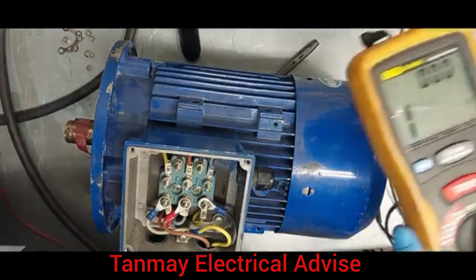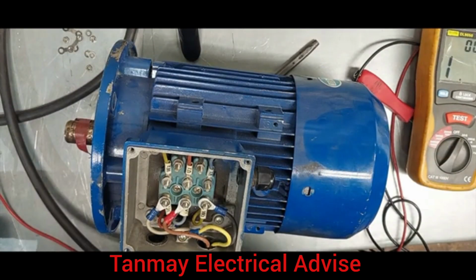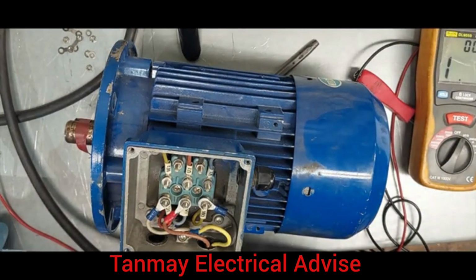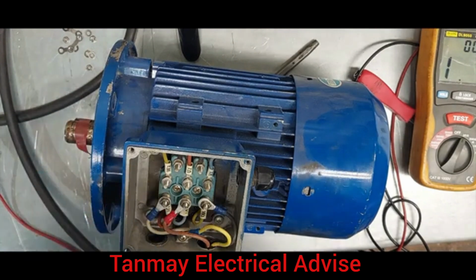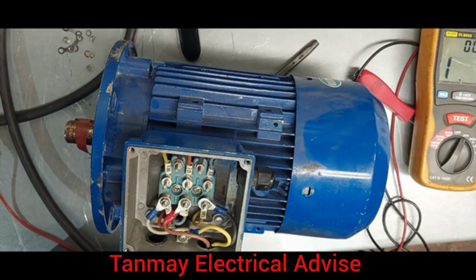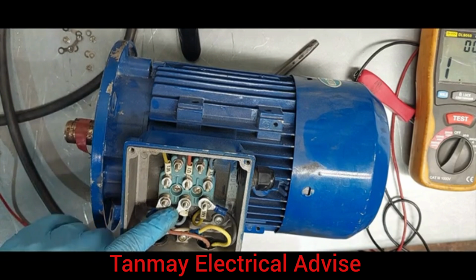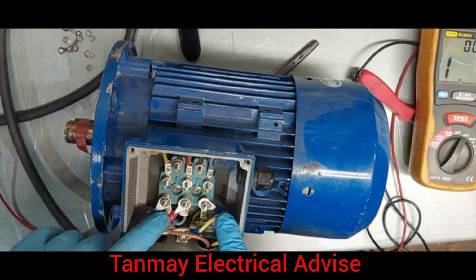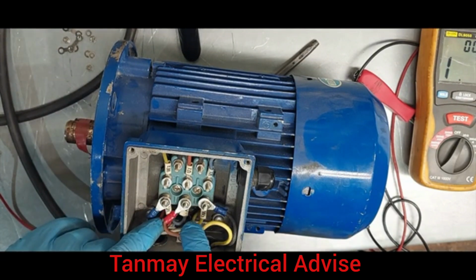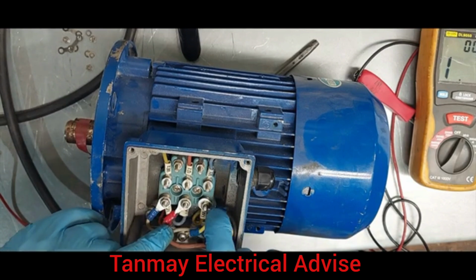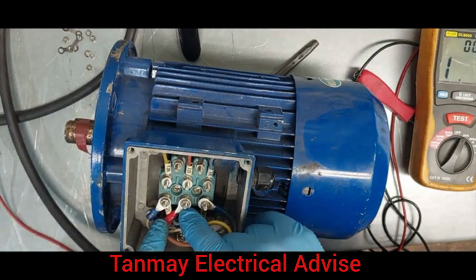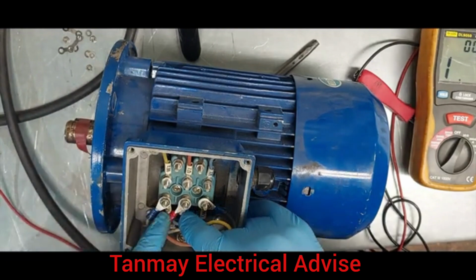What this continuity test checks is to make sure that there's no breakage, and there's no breakage. So now we're going to test to see if there's leakage to earth. In order to check if there's leakage to earth, we must disconnect the mains cable so that we do not inject high voltage into our components.